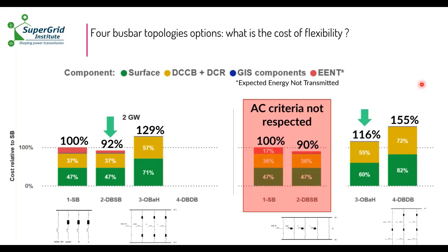But then if the block type is of 3 gigawatts, sorry, I forgot the title here. This is for a 3 gigawatt block type. So if there is a fault on this bus bar, you will lose 3 gigawatts. So if you remember the adequacy, the AC system criteria, you cannot afford to lose this amount of power. So this will not even be considered. It's not feasible to use this configuration: the single bus bar, single breaker.